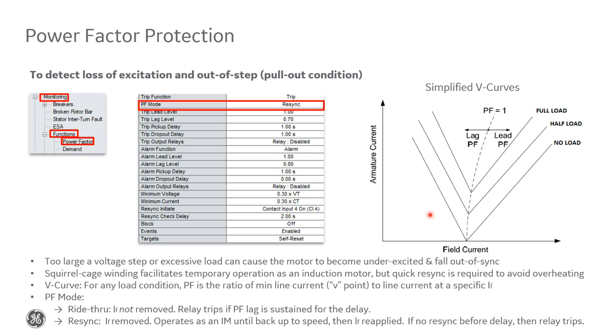So the idea is we generally are okay with operating to some extent in this leading power factor direction. Protection-wise, we often won't trip on that unless it's severe. What we're mainly worried about is if we have too large a step in supply voltage or an excessive change in load, the excitation of either the stator or rotor windings could swing too far off from the other and break the coupling or fall out of sync.